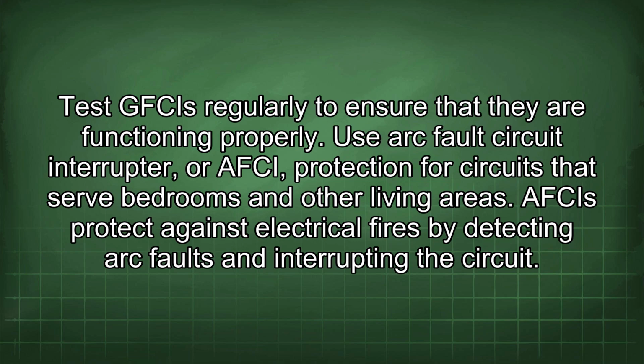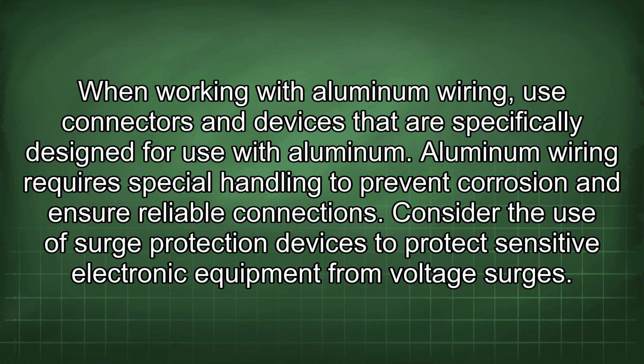Use arc fault circuit interrupter, or AFCI, protection for circuits that serve bedrooms and other living areas. AFCIs protect against electrical fires by detecting arc faults and interrupting the circuit. When working with aluminum wiring, use connectors and devices that are specifically designed for use with aluminum. Aluminum wiring requires special handling to prevent corrosion and ensure reliable connections.